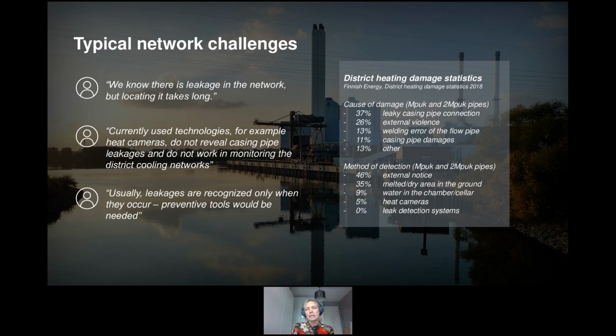But what we can see is that 37% of the leakages are actually in the casing pipe connection in this kind of pre-insulated piping system. So it's a wrong interpretation that only old pipes would be leaking. We can see leak cases also in the newer pipes, especially when it comes to casing pipes.